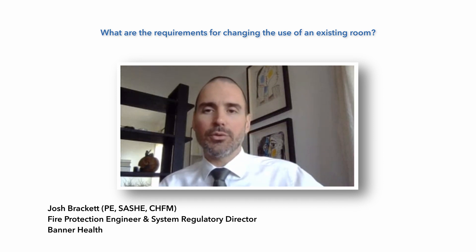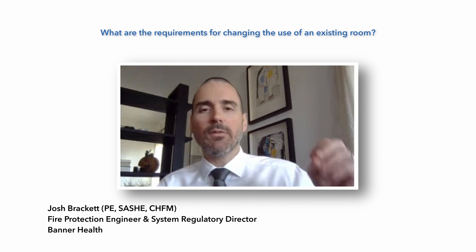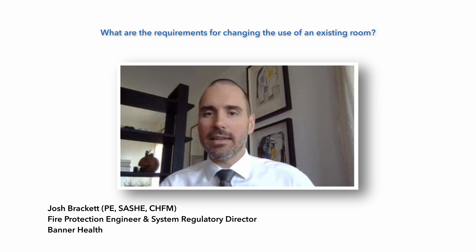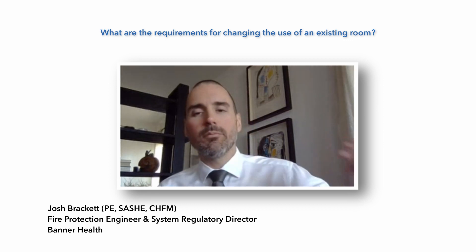The biggest issue that I see when renovating a space and changing that use is that chapter 43 specifically says: where you are renovating a space greater than 250 square feet, and it's going to be used as a hazardous area — which is defined in chapter 18 — then you have to meet the new occupancy criteria.